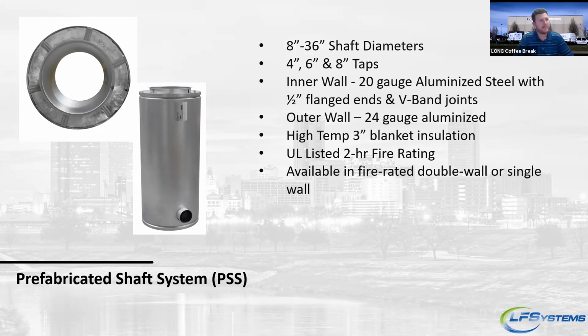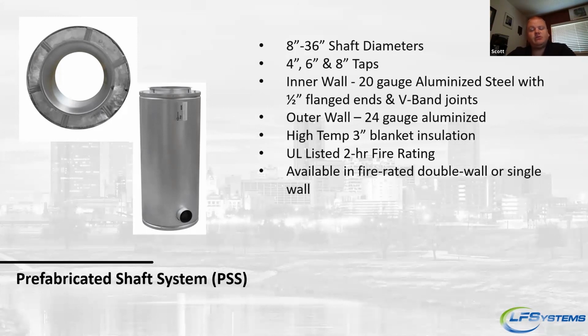Does this qualify for zero clearance to combustibles? So UL doesn't have a listing for zero clearance to combustibles for a shaft per se. They use fire ratings of 1 and 2 hours, and this is rated for 2 hours. It is, however, built to the 2-hour or to the zero clearance standard of factory built grease duct.